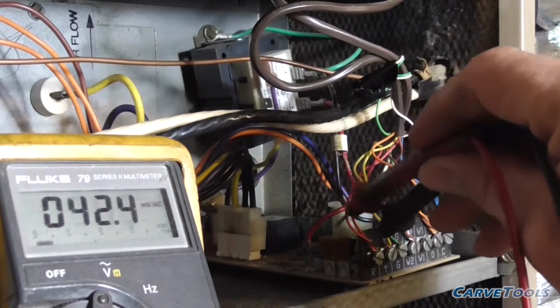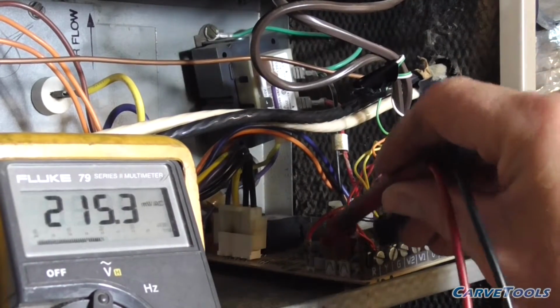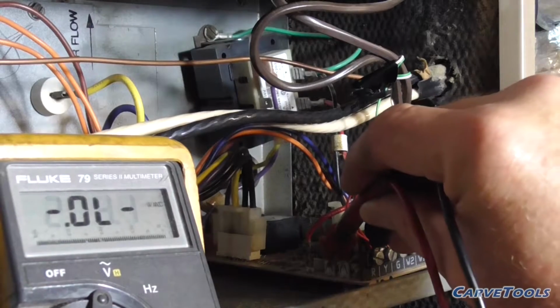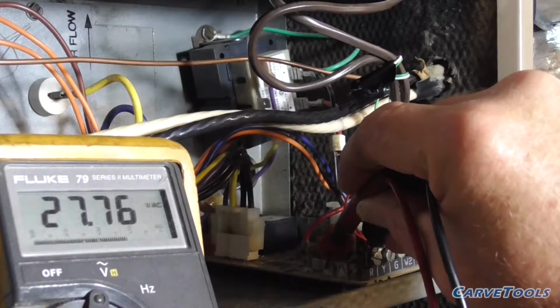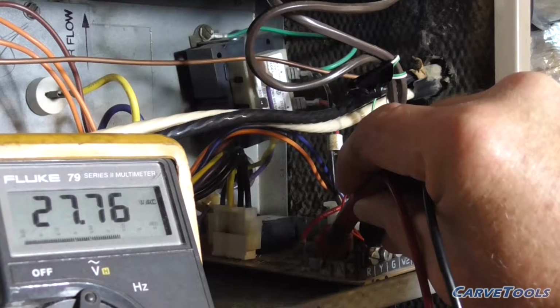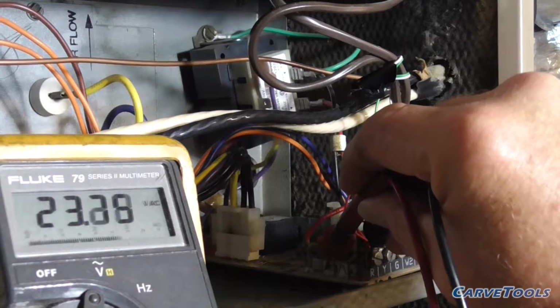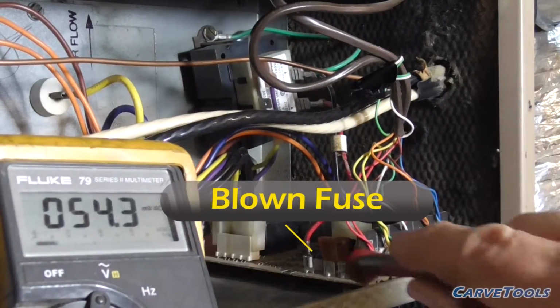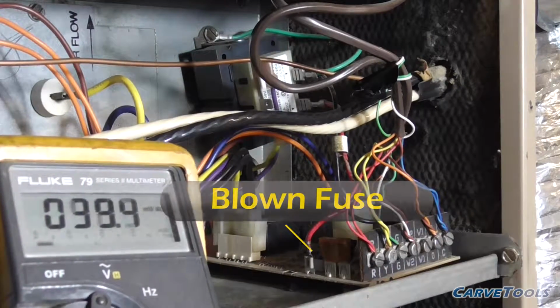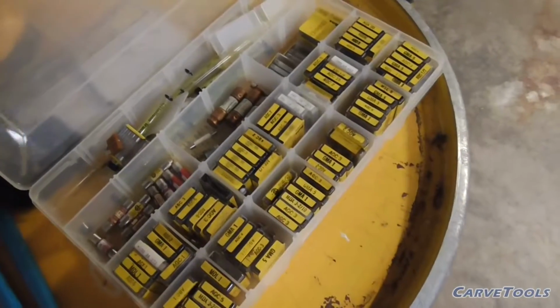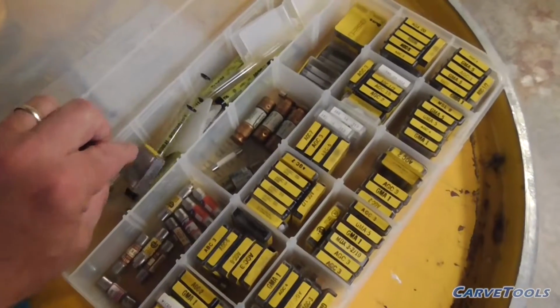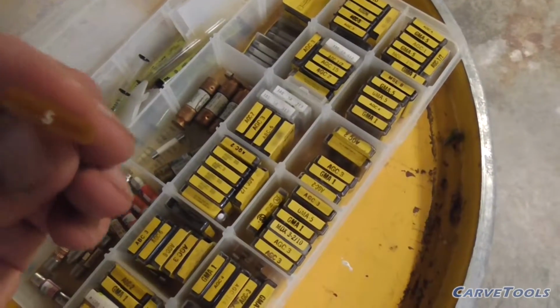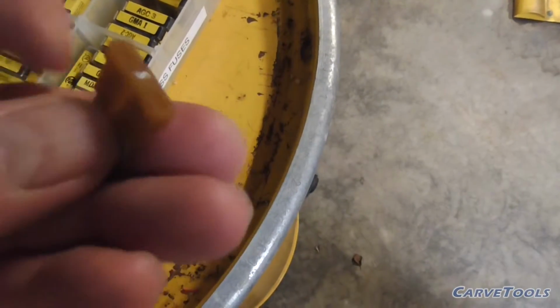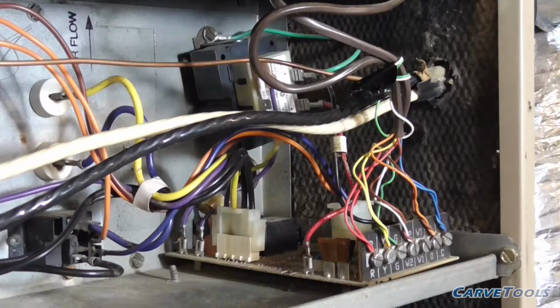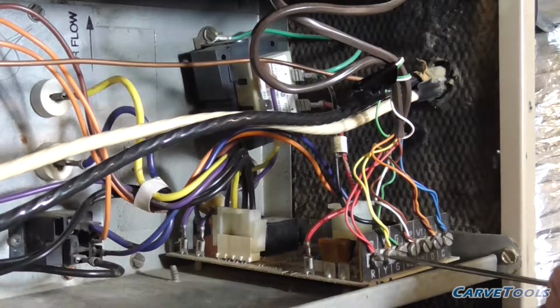Alright, so far I know there is no control power to the circuit board, but checking across the output of the control transformer, I have 28 volts. So this indicates to me that the fuse is blown. I disconnect the circuit breaker to the air handler. Looking in my fuse assortment, I actually had one 5-amp fuse just like I needed. I replaced the fuse and turned on the circuit breaker, and it blew. So there's a short somewhere.